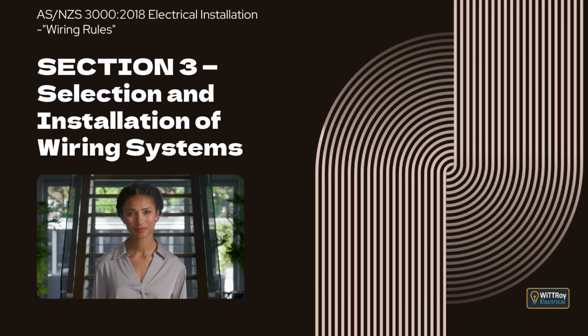This clause explains that a catenary must provide even support along the cable run, be made from materials that resist corrosion and deterioration, be securely fixed at each end, be capable of withstanding expected mechanical stresses such as wind or ice, and be installed at a height that prevents danger to people, livestock, or damage to the cable. Where the catenary forms part of the cable, it must be installed in accordance with the manufacturer's instructions.